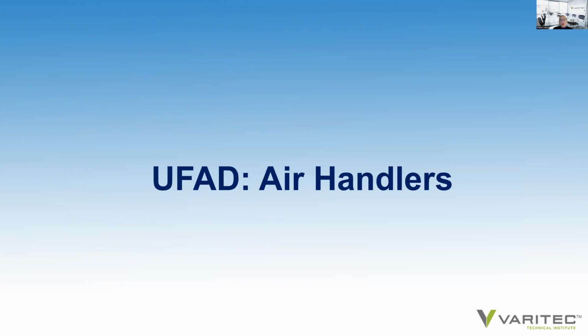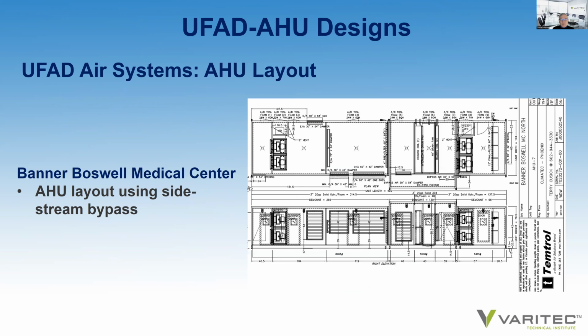So what are the air handlers that service underfloor air systems? Well, I can assure you they're not your conventional medium pressure VAV air handlers. It would adopt the same type of air handler layout possibly as we found in displacement ventilation. Side stream bypass is an effective solution whereby a plenum with a modulating damper located before the cooling coil is provided, and that plenum discharges after the coil.